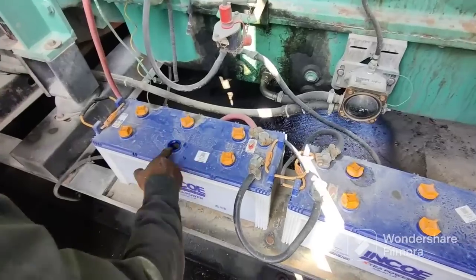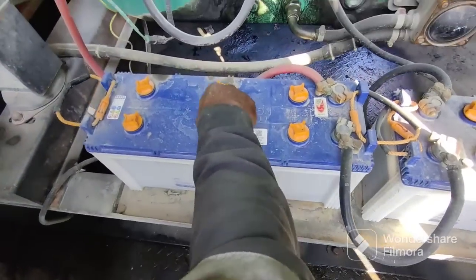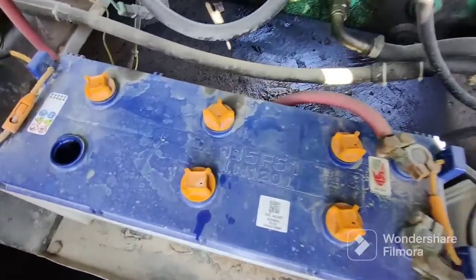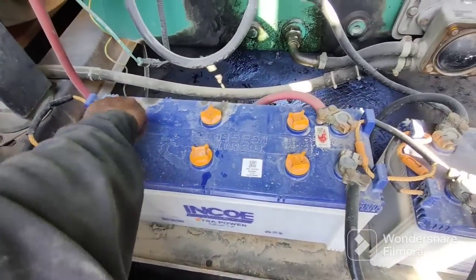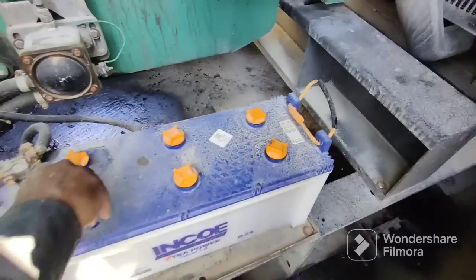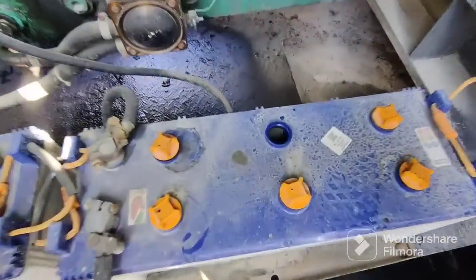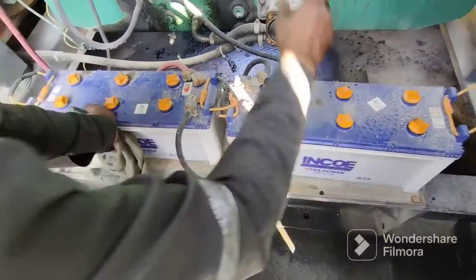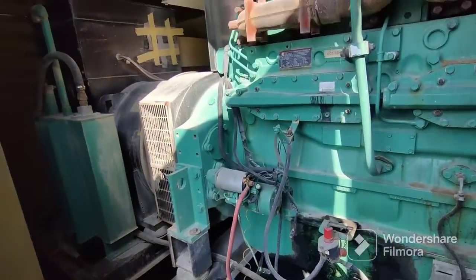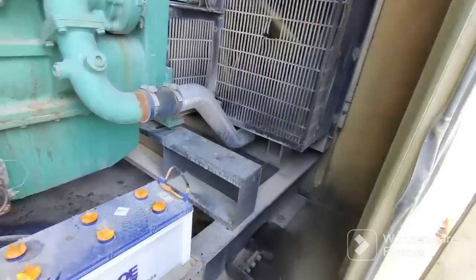During generator service you should also check the batteries. Check if there is acid or water — check the water level. You can see here the water is full. Check the other battery also — the water level is okay, it is fine. Use water to top up if needed. Check the water level on all batteries. You can see the batteries are connected in series connection to complete 24 volts.